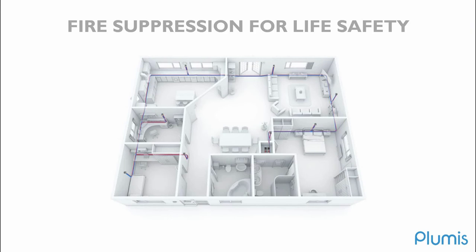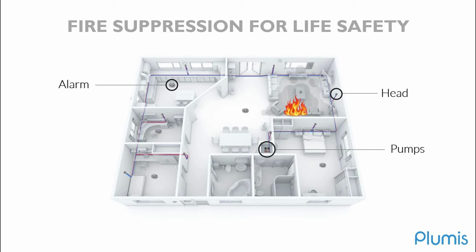So, what's an Automist installation? Well, in an apartment just like this, you'll see our heads distributed throughout the property. They're all connected up via a dry pipe. You have a pump which puts the water up to pressure when the system activates. And then you've got a key part, which is mounted detectors, which is the initial trigger for the system. So in an emergency, you'll have that fire growing within the space, and the nearest alarm will send a message to the nearest head, and then that head will start scanning the room.